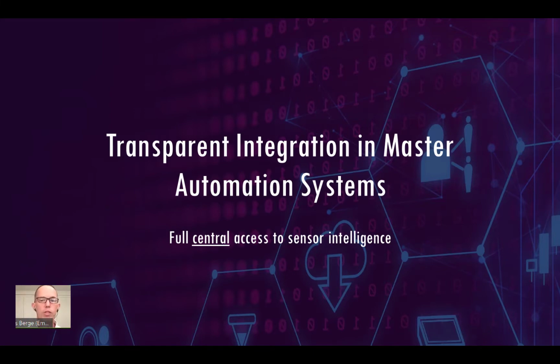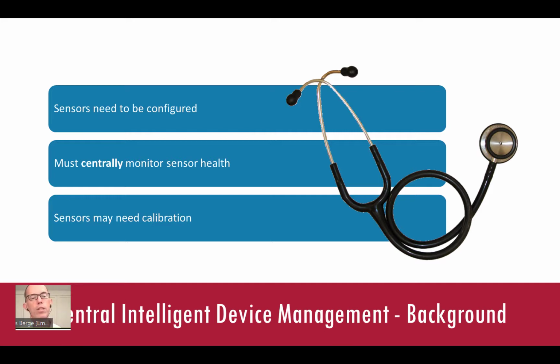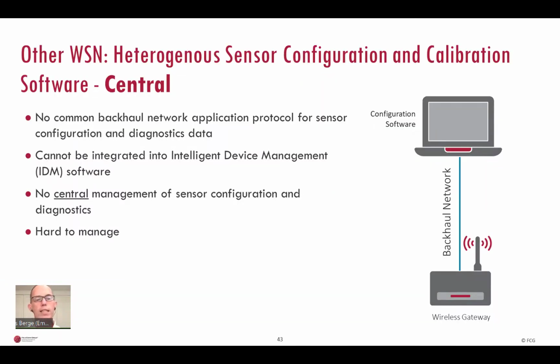Integration with intelligent device management system is important once you have lots of sensors. Just like wired sensors, wireless sensors need to be configured for the use case. You may need to monitor the self-diagnostics in the sensors, and from time to time, sensors may need calibration. Most wireless sensor network technologies do not have a common backhaul network application protocol for sensor configuration and advanced diagnostics data. Therefore, these sensors cannot be integrated into the plant's existing intelligent device management, or IDM, software. Note that even if you could map additional sensor data to Modbus or OPC to bring it into software, it would be impractical to do it and maintain it for all the information in all sensors. Other technologies have no solutions for centrally configuring sensors from multiple vendors. So be careful.